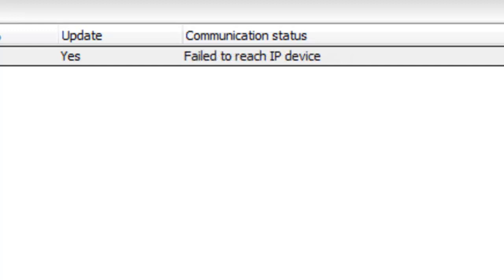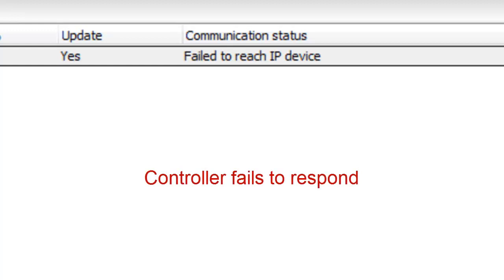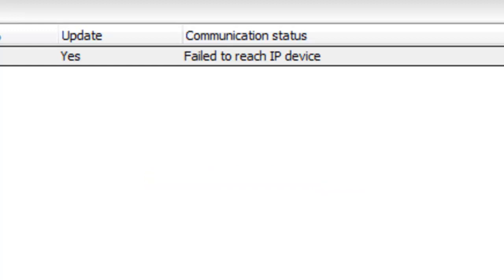Failed to reach IP device. This one indicates that the controller was seen on a network, but for some reason fails to respond. The most common causes are the controller needs to be defaulted before trying to establish communication, or it has the wrong Entrepass gateway programmed.